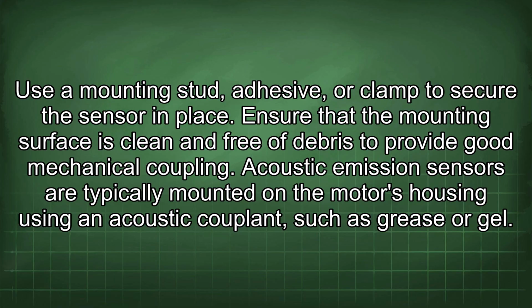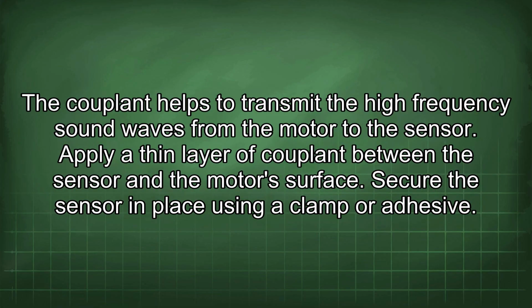Acoustic emission sensors are typically mounted on the motor's housing using an acoustic couplant, such as grease or gel. The couplant helps to transmit the high-frequency sound waves from the motor to the sensor. Apply a thin layer of couplant between the sensor and the motor's surface. Secure the sensor in place using a clamp or adhesive.